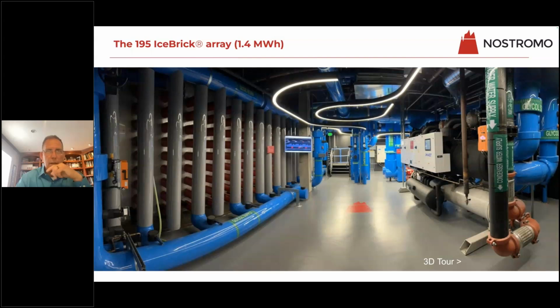This installation is what we built in the basement of the Beverly Hilton Hotel. Pretty nice looking room, and it fully charges and discharges every single day. The IceBricks you see on the left, behind all the insulation and covering, are 1.4 megawatt hours equivalent, and they charge and discharge the building every day. On the right is a charging chiller, and behind the vertical pipes is a heat exchanger. Those are the three main elements, aside from the controls, which aren't shown on screen.